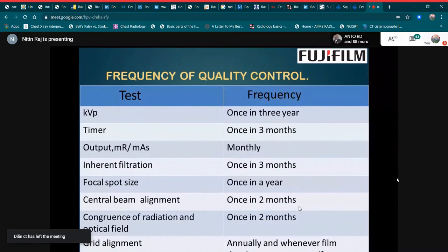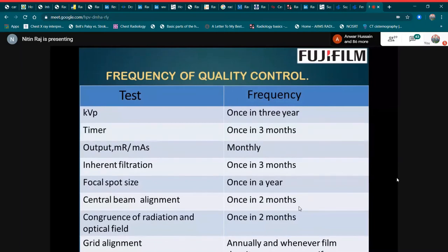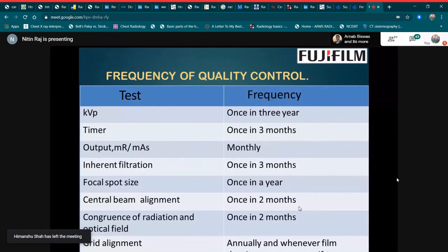Next is the frequency of quality control tests. kVp testing should be done once every three years. Timer checking should be done once every three months. Output should be checked monthly. Inherent filtration should be checked once every three months. Focal spot size should be checked once a year. Central beam alignment should be checked once every two months. Concurrence of radiation and optical fields should be checked once every two months. Grid alignment should be checked annually and whenever film density appears non-uniform.